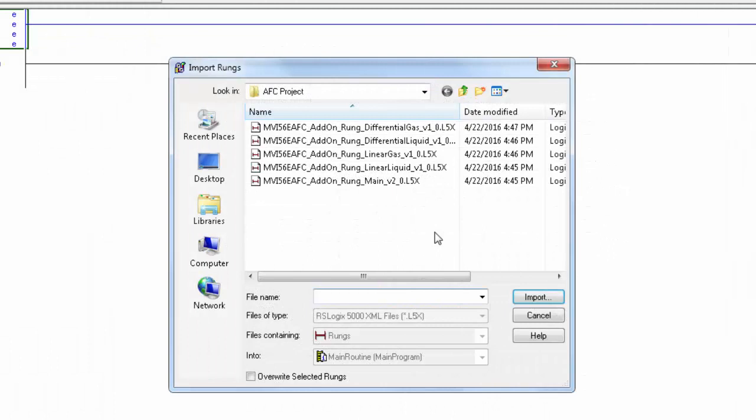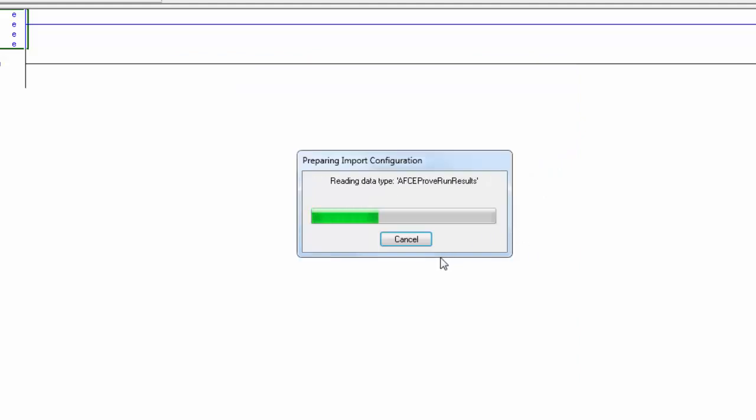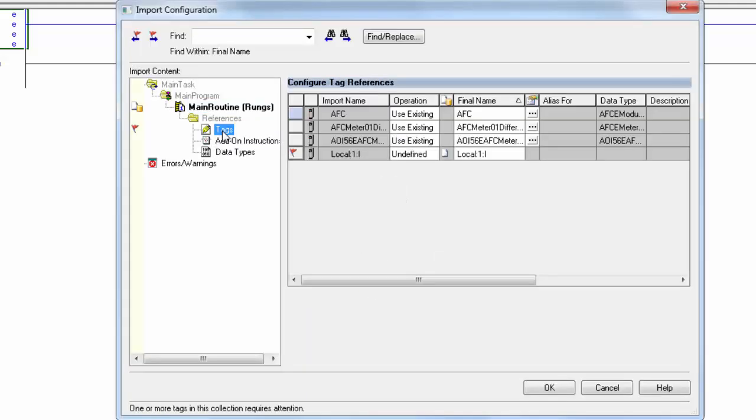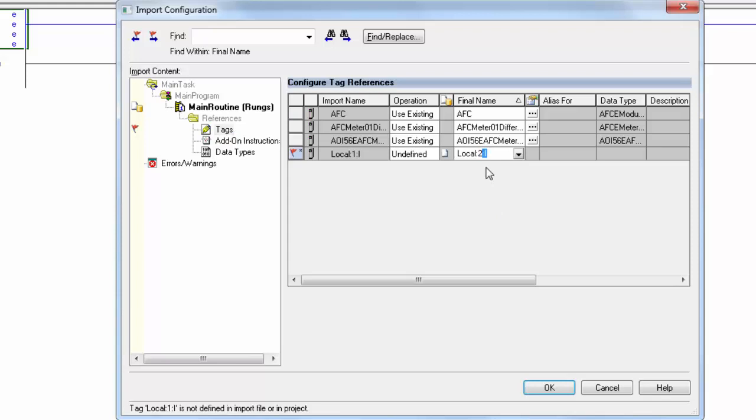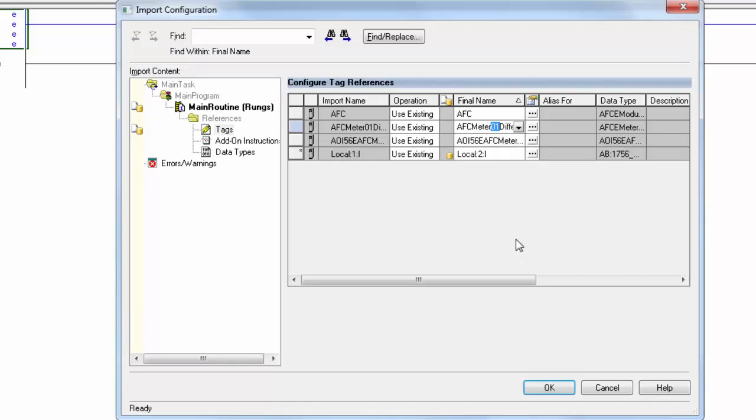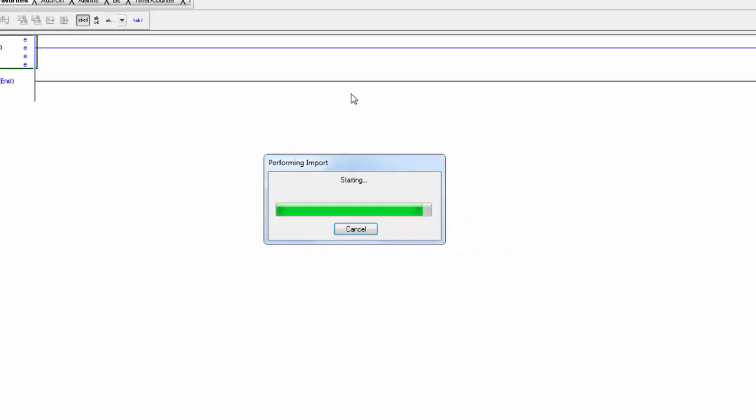In my example, I have 2 meters. I'll be getting readings of Differential gas pressure from a Differential or orifice meter, so I will use the Differential gas AOI. In the Import Configuration window that opens, if you click on the Tags section, you can see the controller tags that will be imported with the AOI. Ensure that the local X tag references are pointed at the correct slot number and that the meter numbers are also set correctly so that no 2 meters have the same meter number. Once you're done, just click OK.